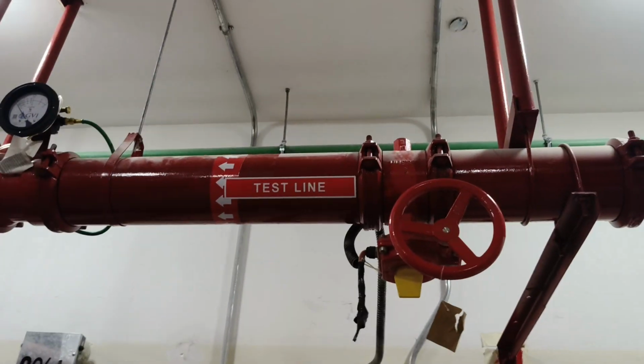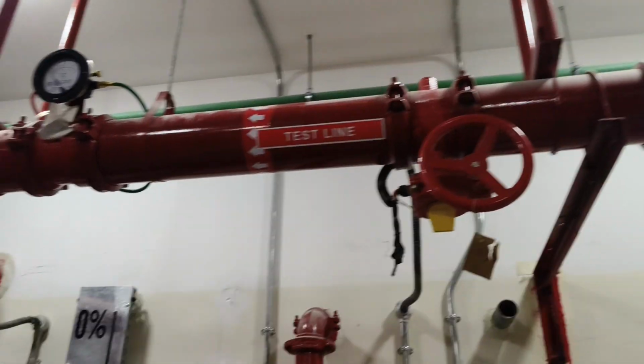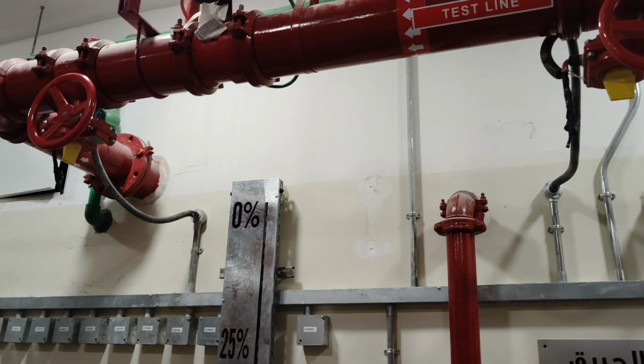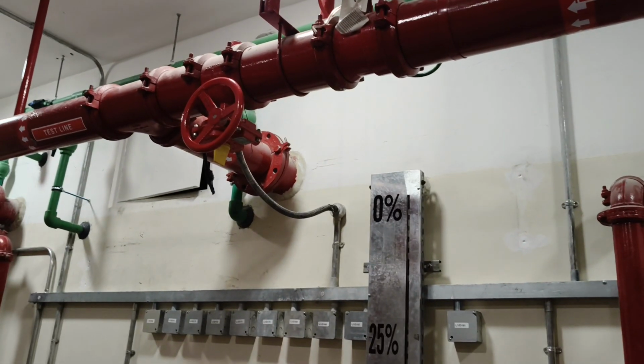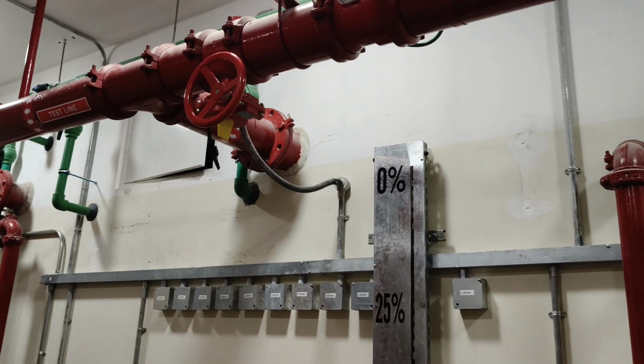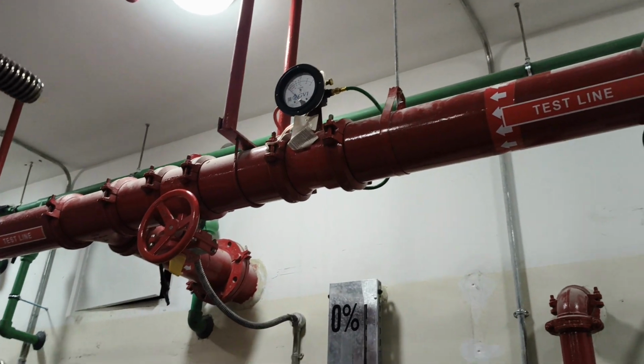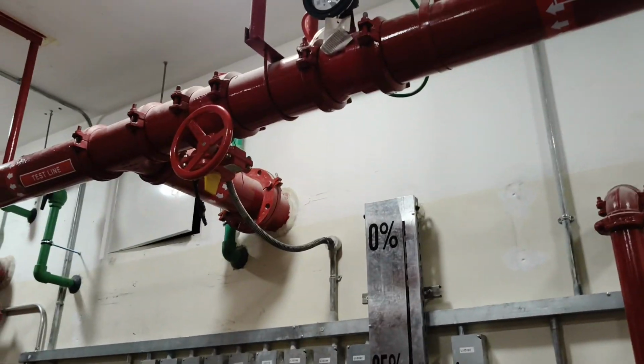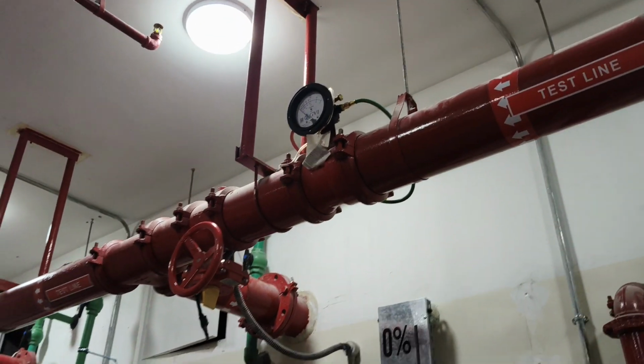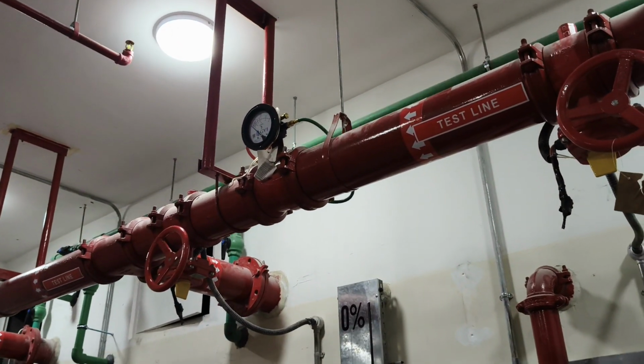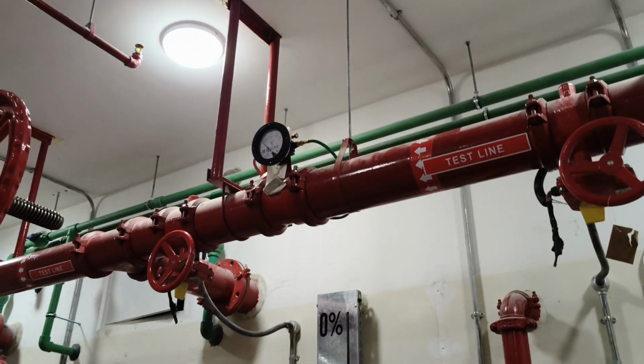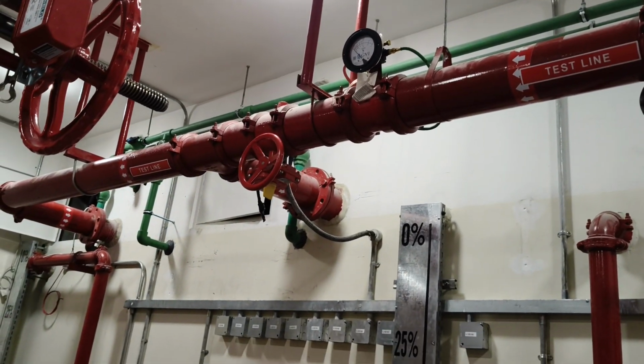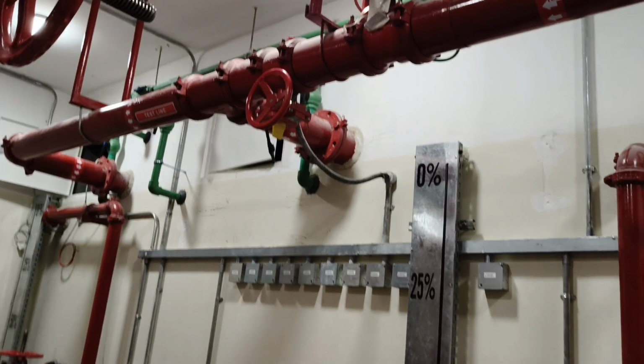So during testing, we did the testing before, right? During testing, you can open the bypass valve and use the throttle valve to guide you through the GPM. It's either the 0%, the 100%, and the 150%, which is the major one that is being looked at anytime that we are doing testing.